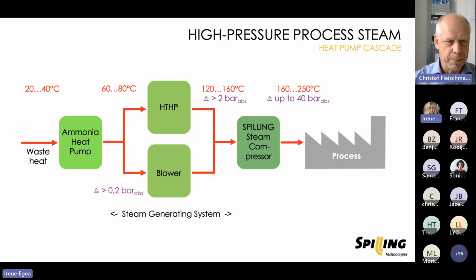At the lower end, you see these ammonia heat pumps, which are state-of-the-art, and which can use low temperature heat of 20 to 40 degrees Celsius and lift this heat to higher temperatures like 80 up to 90 degrees Celsius maybe. Heat sources in this lower temperature range might be, for example, cooling water, also exhaust heat from chillers or refrigeration machines, or heat from the surrounding landscape, like river water, or also geothermal heat. Therefore the ammonia heat pumps are existing.